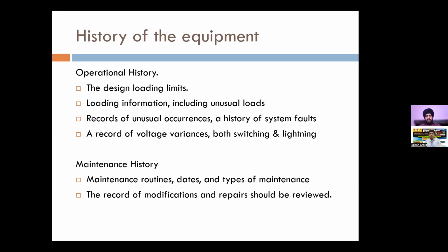Now that you have established all the raw data which has been seen and which has also been tested through the LV test result, now you need to verify or establish the root cause. So while establishing the root cause, you need to also consider the history of the equipment. History of the equipment, not as in this particular equipment, but also its sister units also, whether that particular design has had similar failures, if there have been some issues observed during testing, or it has come to light recently if there have been some issues. So all those factors also should be considered while hypothesizing or formulating any hypothesis of the cause of the failure.